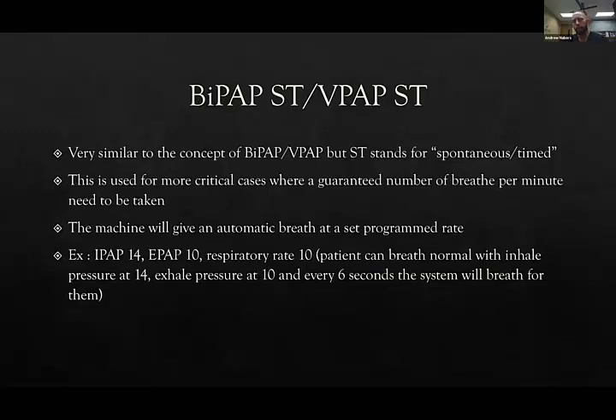BiPAP ST. So as I was mentioning with the BiPAP, the variable pressures, inhale, exhale pressure. The ST stands for spontaneous timed. Basically what that means is, as I put an example down here, this IPAP stands for inhaled positive airway pressure. It's the pressure you would breathe in with. Now, a pressure of 14 is kind of a moderate pressure. The EPAP, or exhaled positive airway pressure, at 10 is the pressure you breathe against. Now, the exhaled pressure keeps your throat open. The inhaled pressure opens everything up. It opens your throat, your lungs.